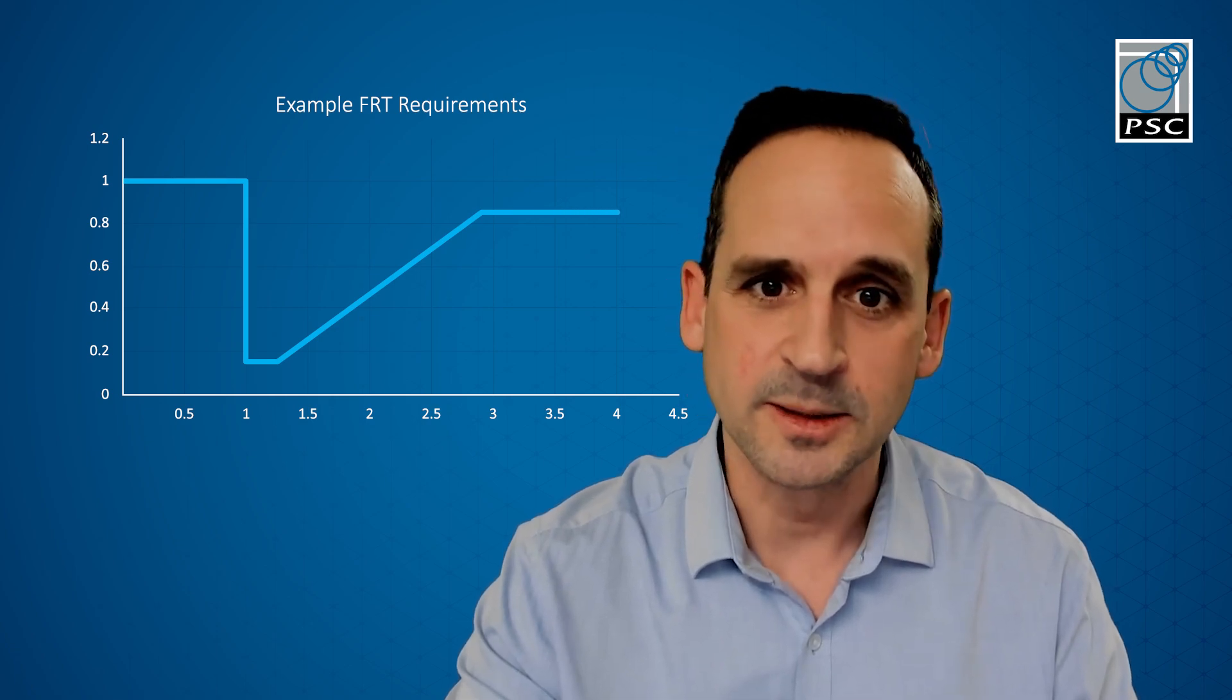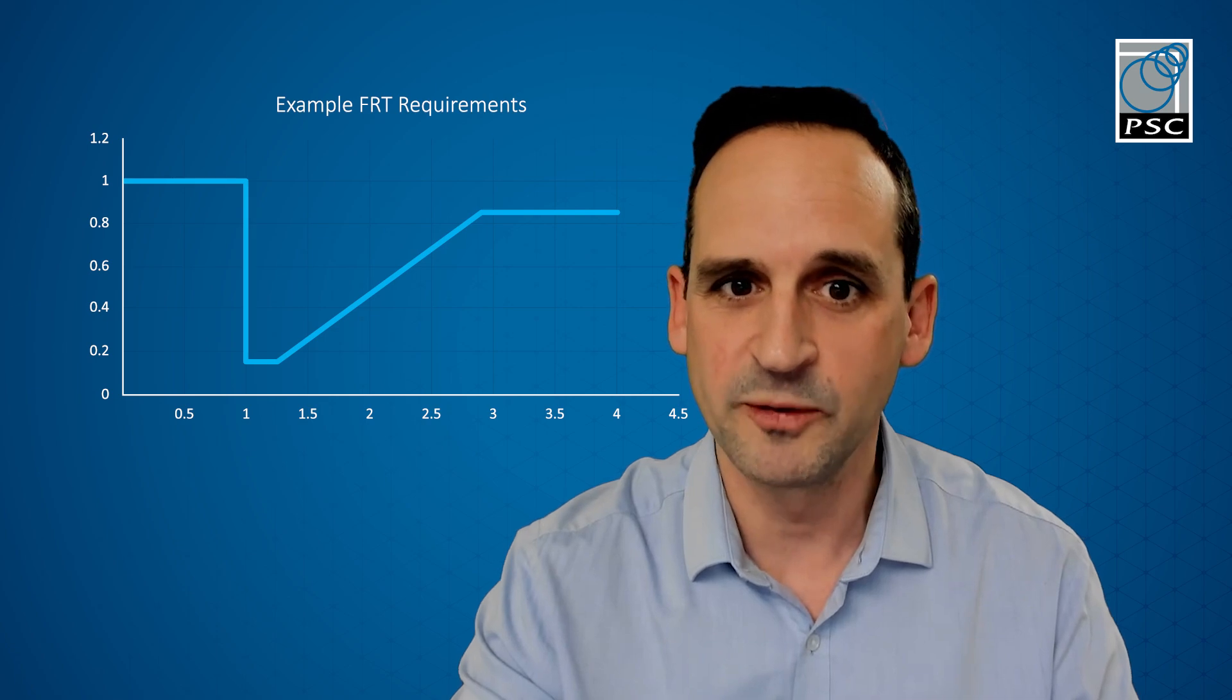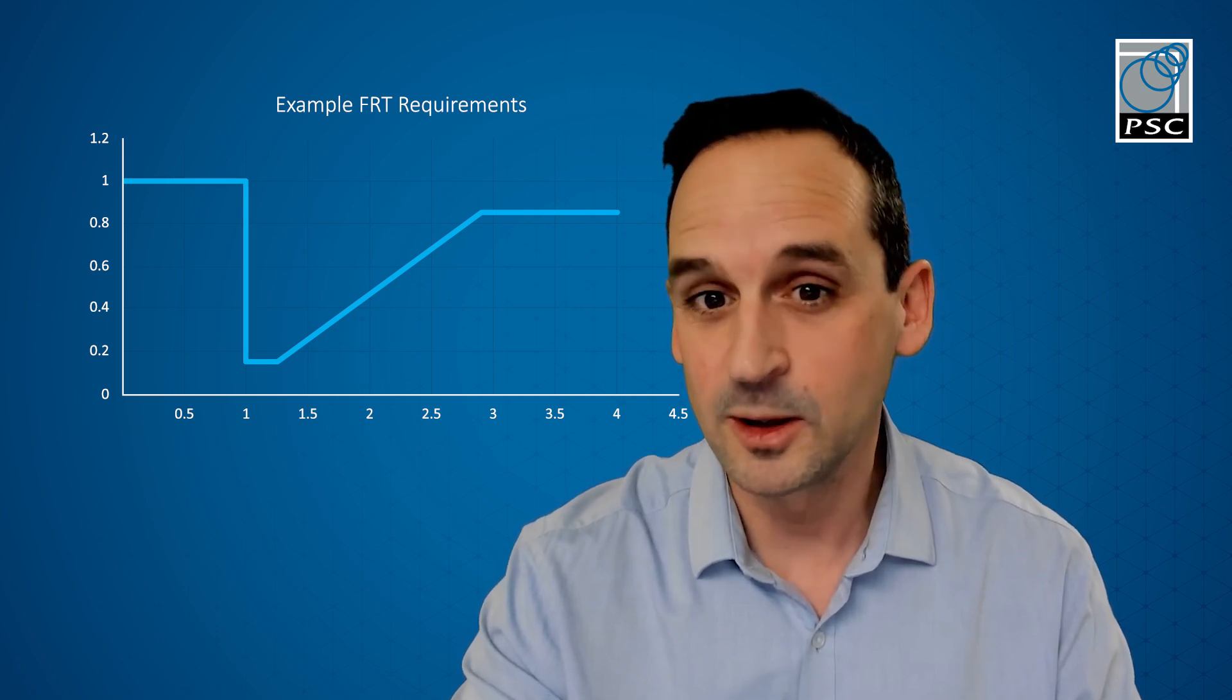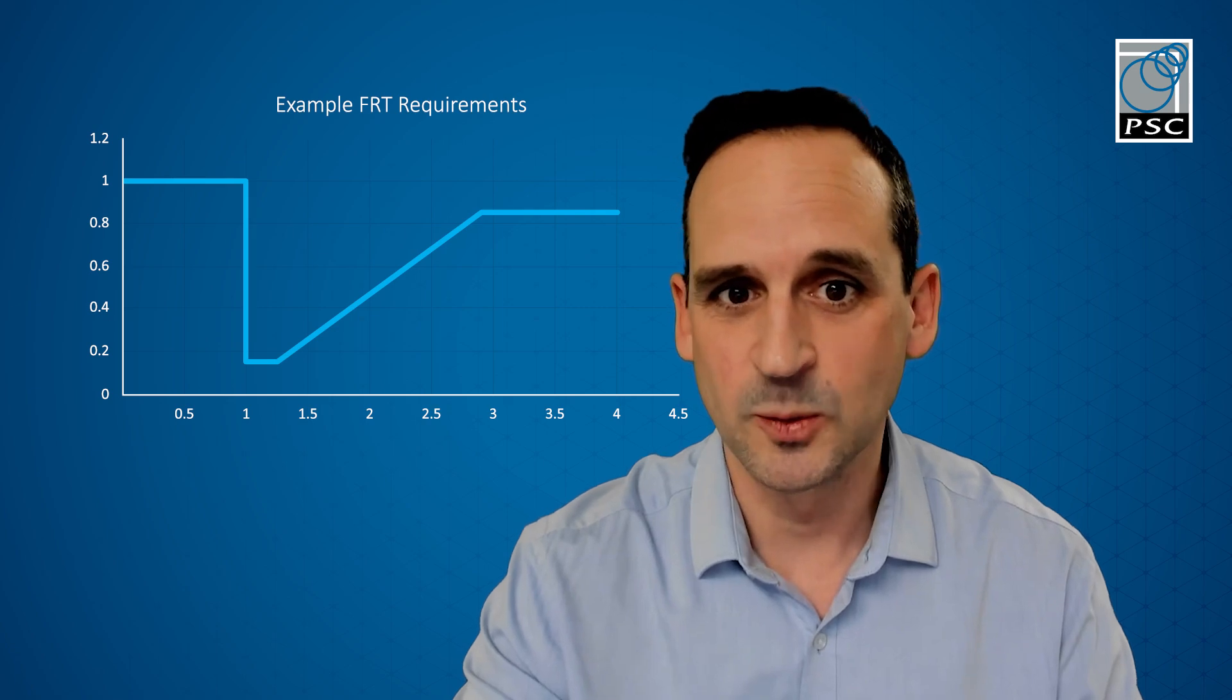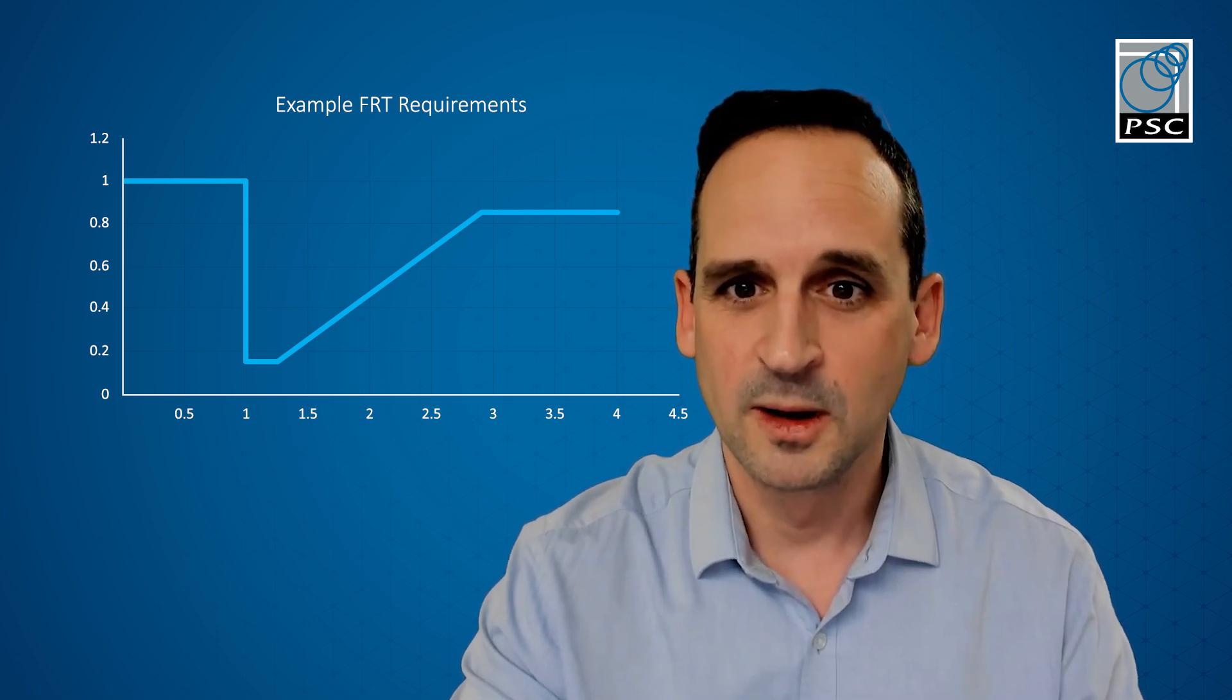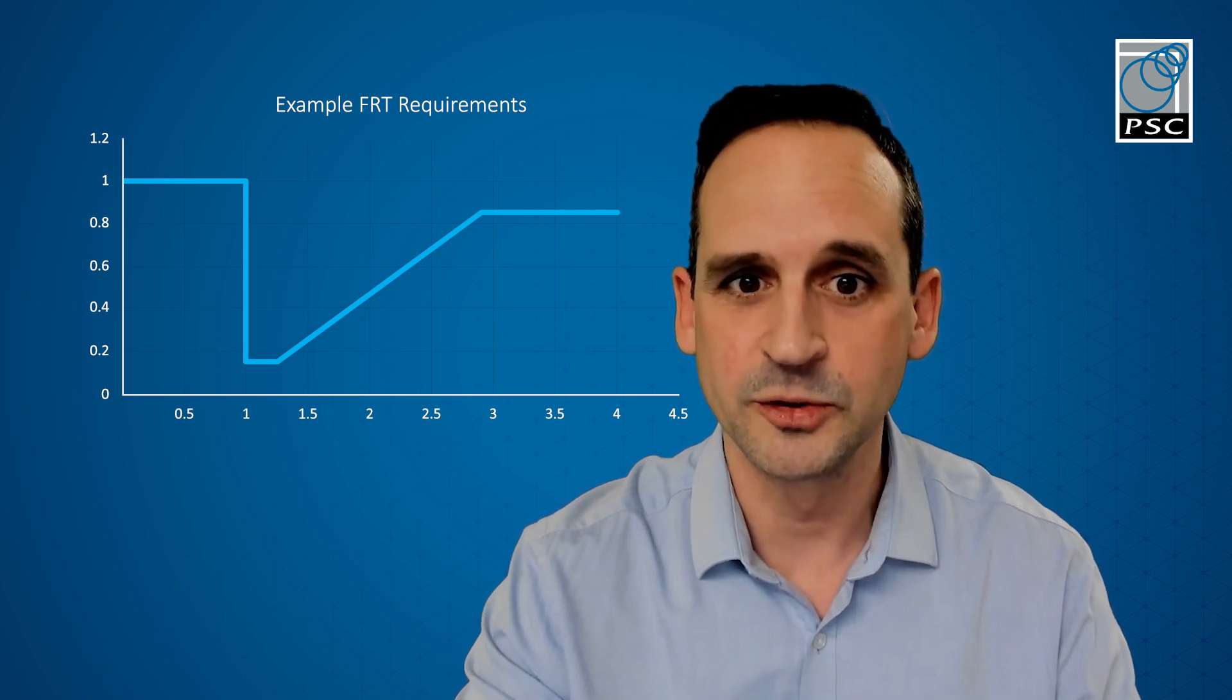What you can see here is a graph that represents a typical FRT requirement which would be found in the grid code. The figure you look at would depend on the type of fault and generator, whether it's synchronous, wind turbine or PV, and also which country you're working in as the details can differ slightly.